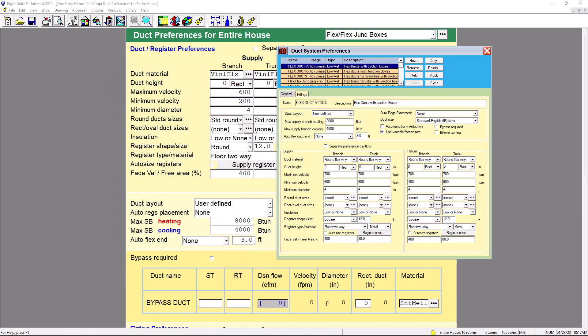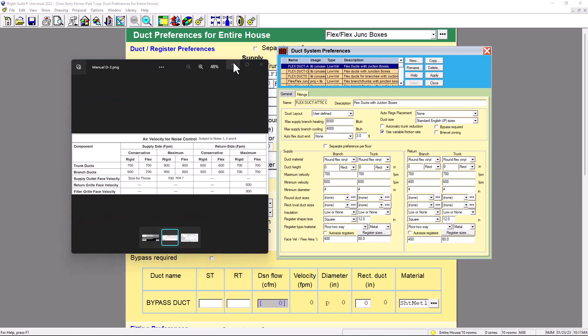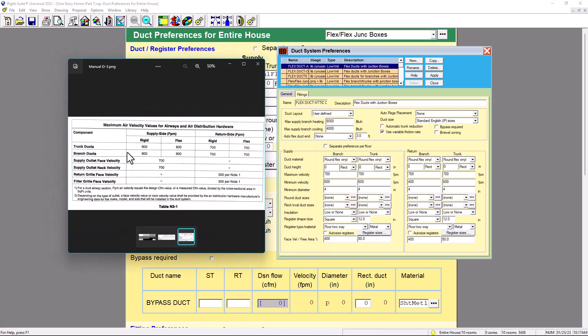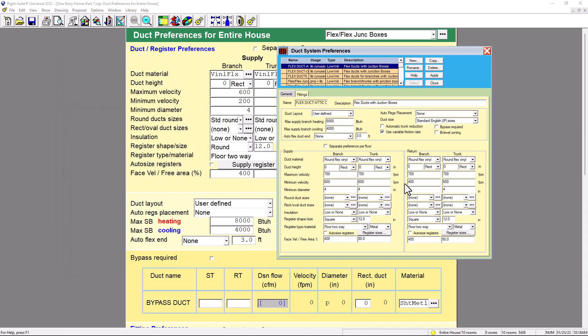The new Manual D version three is telling you only 900 for supply and 700 for return. But 900 is kind of a lot, especially for noise issues. For now let's use 700 maximum and 600 minimum - let's be conservative. So for returns, we're going to have 400 minimum and 700 maximum for branch, and 600 minimum and 700 maximum for trunk. My minimum diameter - let's leave it at 4 inches for all.